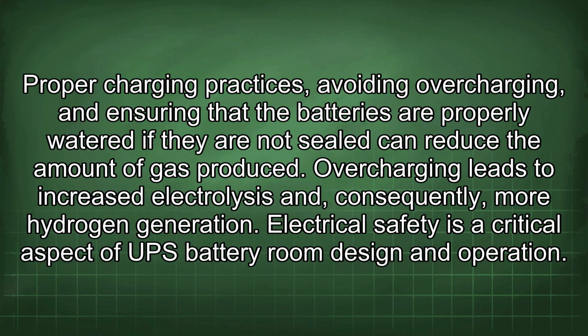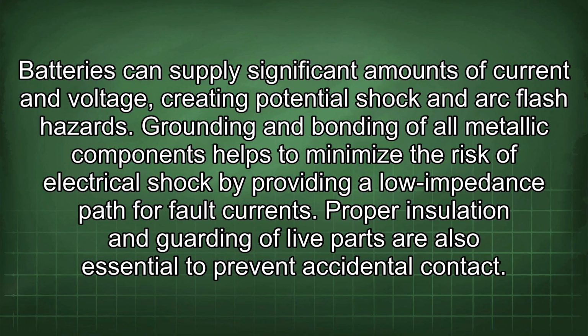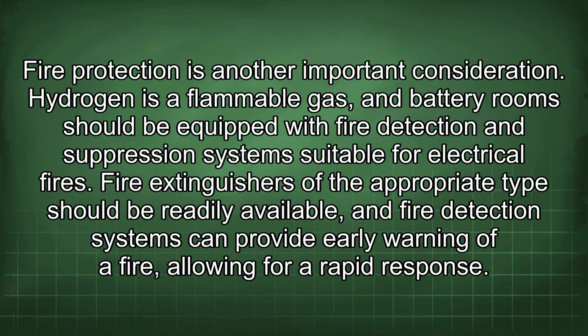Electrical safety is a critical aspect of UPS battery room design and operation. Batteries can supply significant amounts of current and voltage, creating potential shock and arc flash hazards. Grounding and bonding of all metallic components helps to minimize the risk of electrical shock by providing a low impedance path for fault currents. Proper insulation and guarding of live parts are also essential to prevent accidental contact. Fire protection is another important consideration. Hydrogen is a flammable gas, and battery rooms should be equipped with fire detection and suppression systems suitable for electrical fires. Fire extinguishers of the appropriate type should be readily available, and fire detection systems can provide early warning of a fire, allowing for a rapid response.